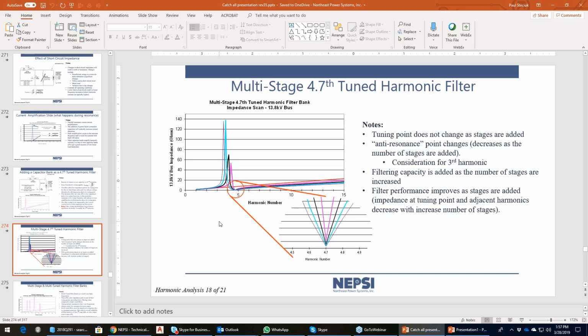So the harmonic that you tune to, whether it's 4.2, 4.7, 4.8, 4.9, there is not a wrong answer. It's just a matter of how close to the 5th you go, and how much harmonic current you will pull in. But you need to be concerned at the 4.2 as much as at the 4.7, 4.8, and 4.9. Tuning below the 5th harmonic is very common, 4.7, 4.8. I show in this curve here that there's a resonance below the tuning point. If you could just imagine sliding this curve slightly to the right, that's what can happen with the tolerances on the reactor. If the reactor comes in with a lower impedance, it's going to slide that curve to the right. If the capacitance comes in off, it can also slide the curve to the right. And as you fail capacitors, it can slide this resonant point to the right.